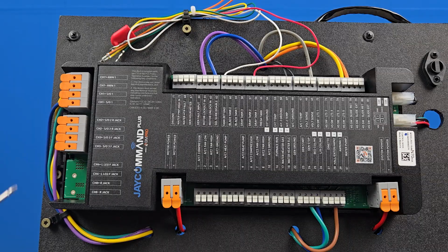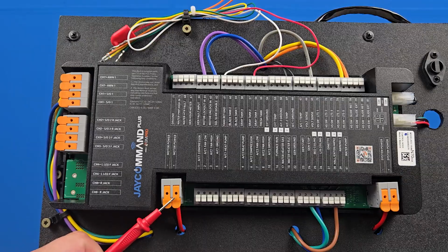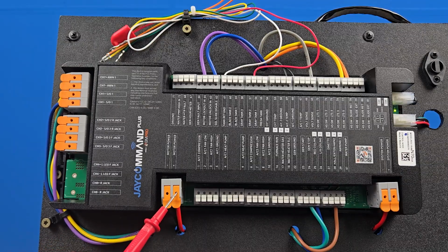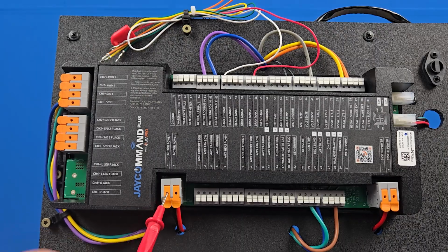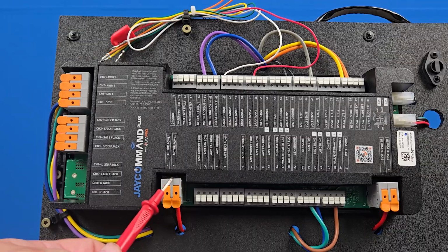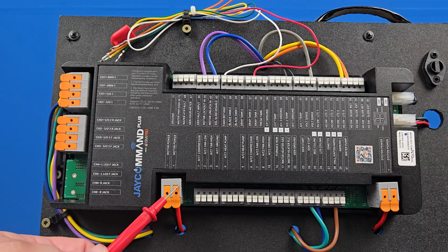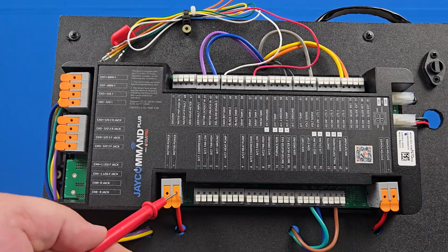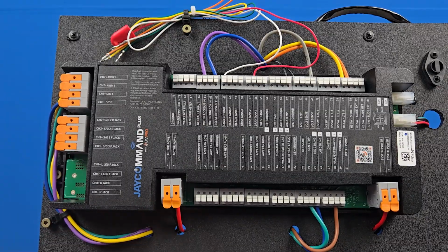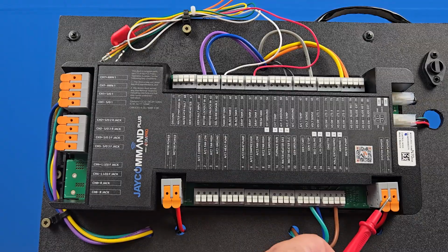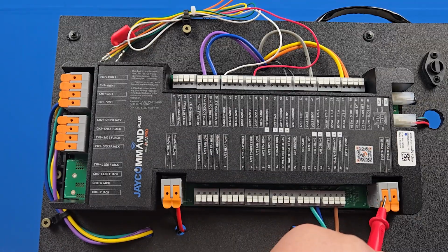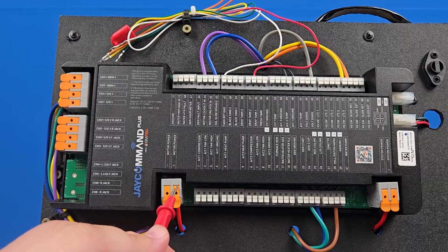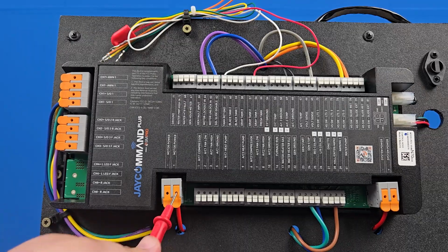On this side over here, we've got our motor power. So our dial that we were looking at earlier directly controls this. And oftentimes in our units, our house power switch or our house disconnect will also control power coming to this portion here. This allows power to be used for applications throughout the unit. So while this is usually pretty low amperage, usually like 10 or 15 amp, this is oftentimes 30 to 50 amps, depending on the unit.